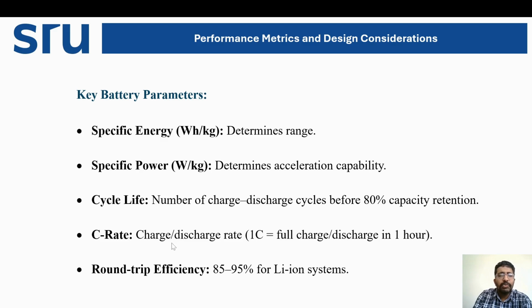Then there's the C rate, which indicates how quickly charging and discharging is allowed. One C rate means full charging or discharging in 1 hour. A 2 C rate means charging or discharging in half an hour, calculated as full capacity divided by the time taken to charge. So 5 C rate means charged and discharged in 1 hour divided by 5, which is 12 minutes. This helps us decide the charging and discharging cycles.